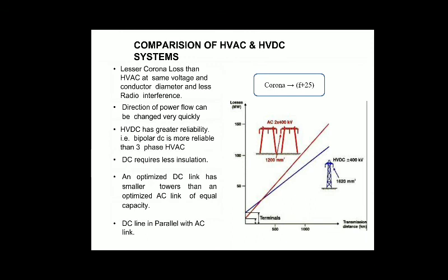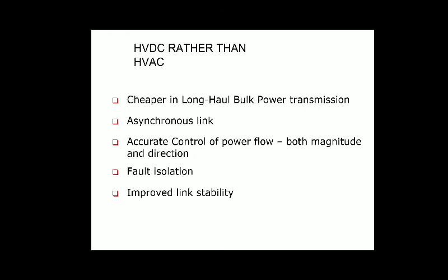HVDC has great reliability — bipolar DC is more reliable than 3-phase HVAC. DC requires less insulation because the peak voltage equals the RMS voltage in DC, so for the same voltage condition, HVDC system wires require less insulation. An optimized DC link has smaller towers than an optimized AC link of equal capacity. HVDC is cheaper in long-haul bulk power transmission, enables asynchronous links, accurate control of power flow in both magnitude and direction, fault isolation, and improved link stability. These are the advantages of HVDC compared to HVAC.